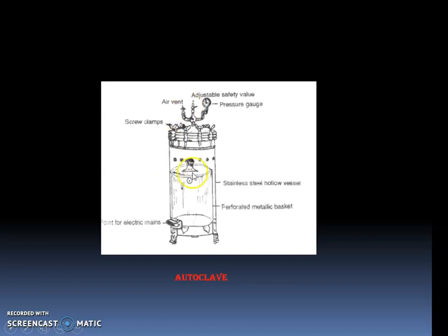So this equipment is the autoclave. It has screw caps which have to be opened to open the lid of the autoclave. This is the air vent. It has a pressure gauge where you can record the pressure, and an adjustable safety valve. It has a stainless steel hollow vessel in which we are supposed to keep the substance which is to be sterilized. It has a perforated metallic basket so that steam is generated from it, and it has a point of electric mains which is attached to the socket for supply of electricity and for the purpose of heating, so that steam will be produced under pressure.